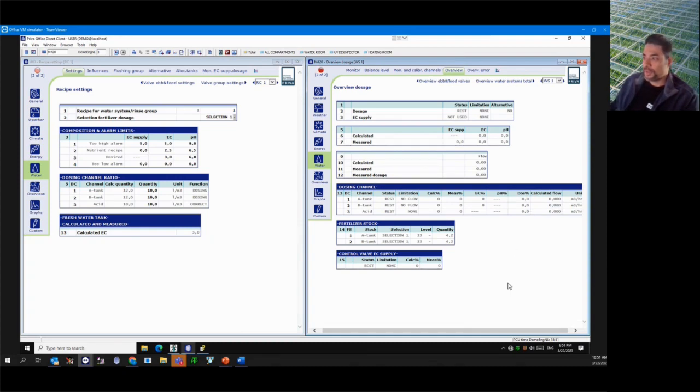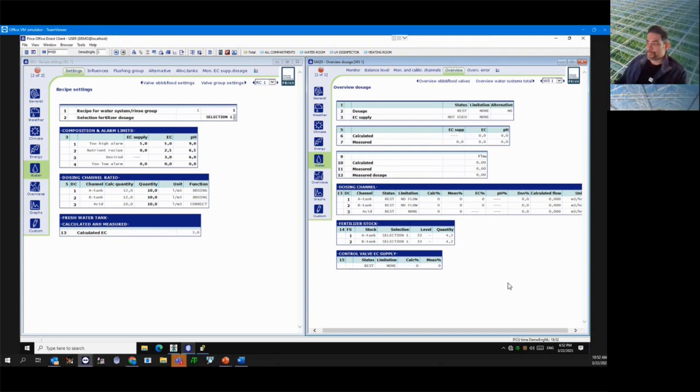Okay. Now, just by rule of how a control system works, if you want to have good control, you don't want to be too far on the low end. So like 1-2% dosing, it's not going to be good accurate control, right? Versus even 90-95% dosing, also not going to be good control. That means your dosing channels are working almost 100%. There's very small room for correction, right?